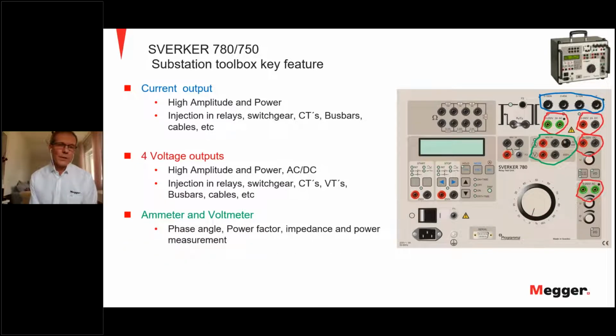Also, it has an ammeter and a voltmeter, and these meters are completely independent from the test set. They can also make calculations between these 2 analog inputs. So you can get the phase angle between the ammeter and voltmeter, or the power factor, impedance, and power measurements. So it's not only a unit where you can inject current and voltage, you can also do measurements. It's like a multimeter. And of course, you have the timer to do the timing test when you're testing relays. Or if you would like to do timing on some other product, that's possible by starting on contact sense and stopping on contact sense, or voltage sense. That's possible to set.